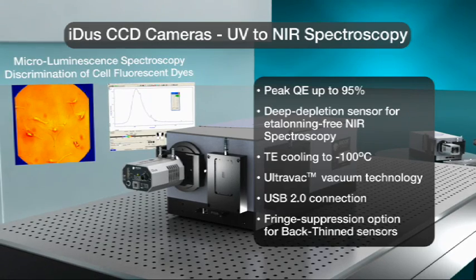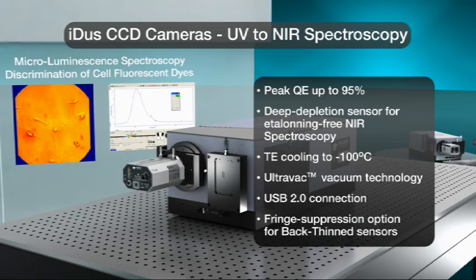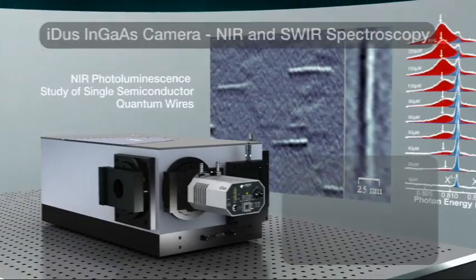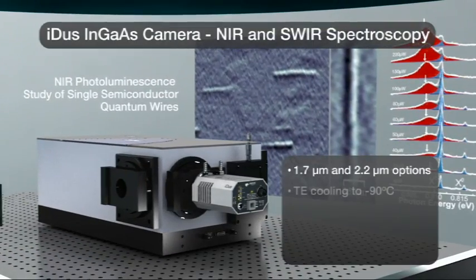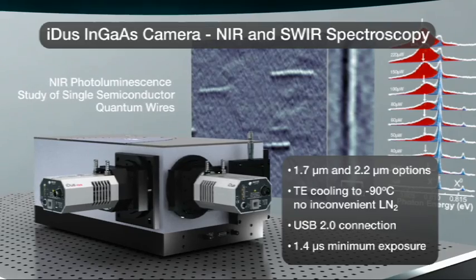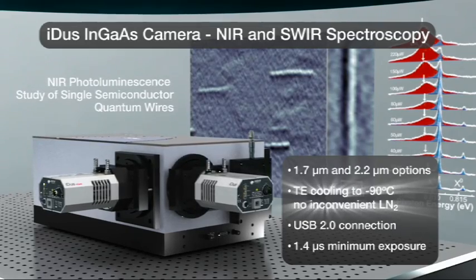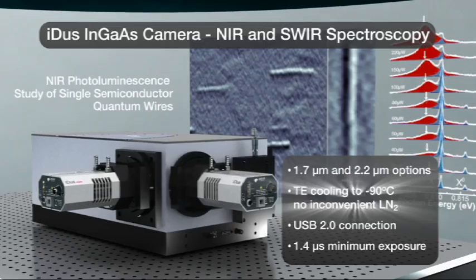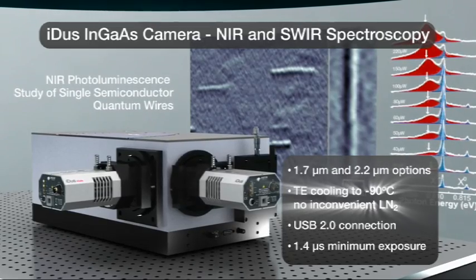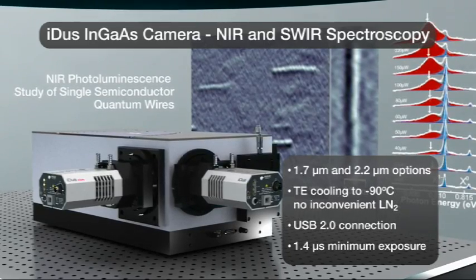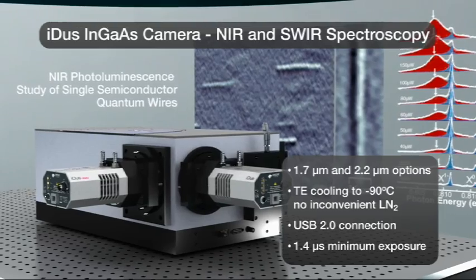The iDus also offers extended near-infrared and short-wave infrared arrays up to 1.7 and 2.2 micrometers. The thermoelectric cooling to minus 90 degrees without the inconvenient use of liquid nitrogen offers virtually no compromise on signal-to-noise performance.